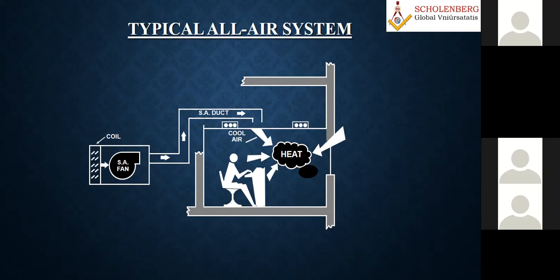He was talking about why we need a compressor in a vapor compression system. He explained it beautifully. Let's say I have R22 gas and I put it in a cylinder. The cylinder's R22 boiling point is, let's say, minus 30, 36, or 39, or whatever it is. So if I keep it in a cylinder and open it slightly, the gas will expand, and when it expands it evaporates and needs cooling.